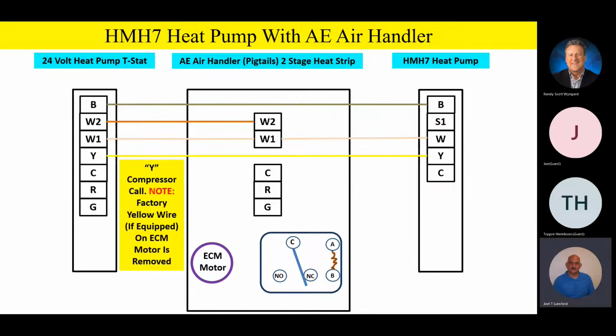The Y terminal on the heat pump thermostat goes straight outside, and this is going to be our compressor call. Now, it's real important on the AE air handler, you're going to have a factory installed yellow wire on the ECM motor. And what you're going to do is remove that wire. So from the factory, you may have a Y or yellow wire on the motor itself, and you're going to remove that off the actual ECM motor, because we're going to do something else with it after a while. So Y from the thermostat goes outside to Y on the outdoor unit.